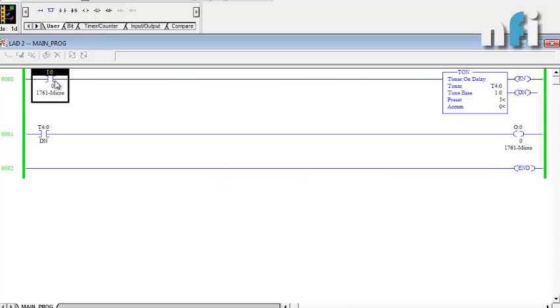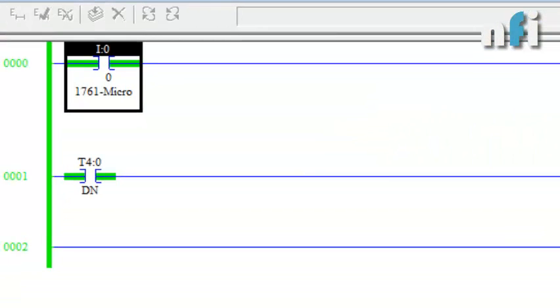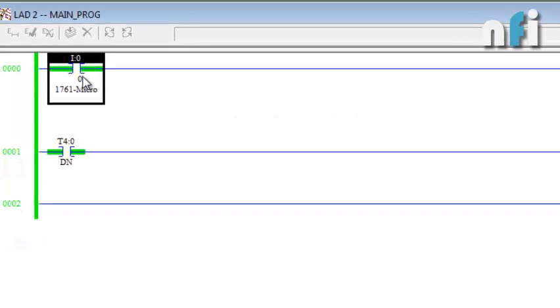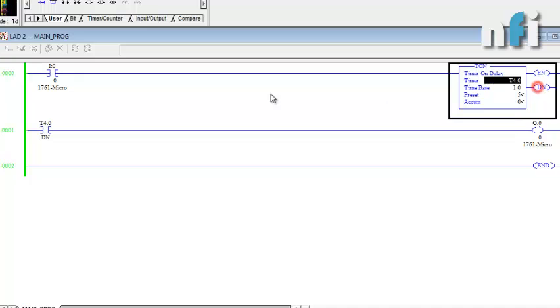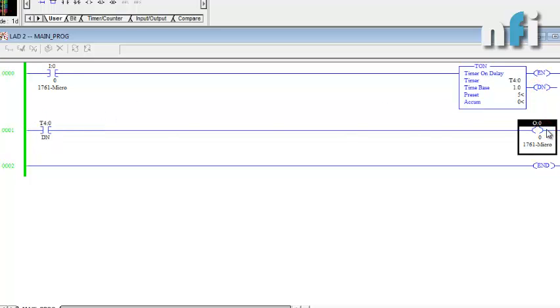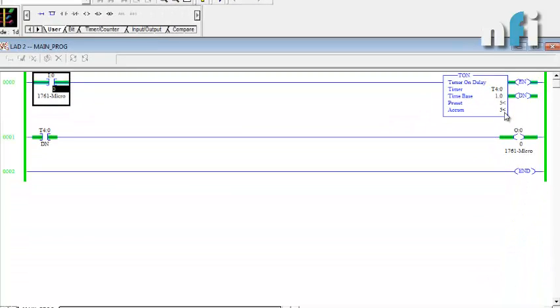IN0 is off so the timer is not counting. Now I'm pressing IN0 — you can see the accumulator has started counting: three, four, five. After five seconds the done bit is on and the output is on. If I release I0, the timer resets itself, the done bit resets, and the output is off. I'll try again — pressing the button, the timer starts counting, and output will be on after five seconds.